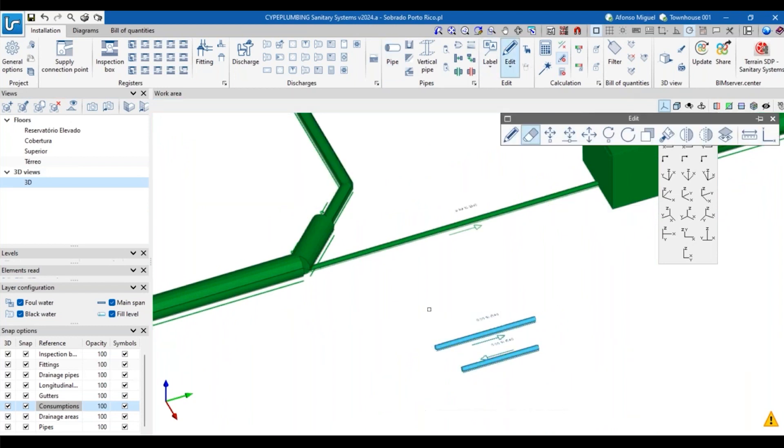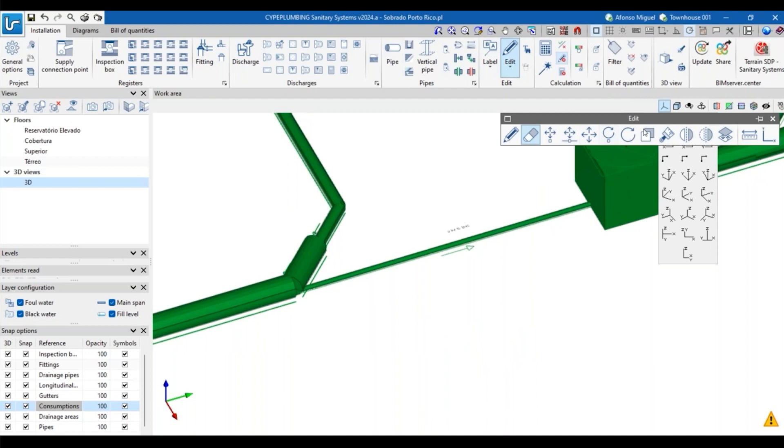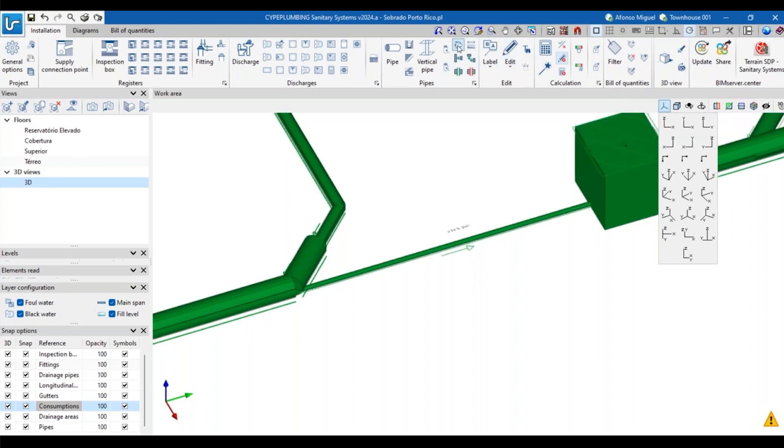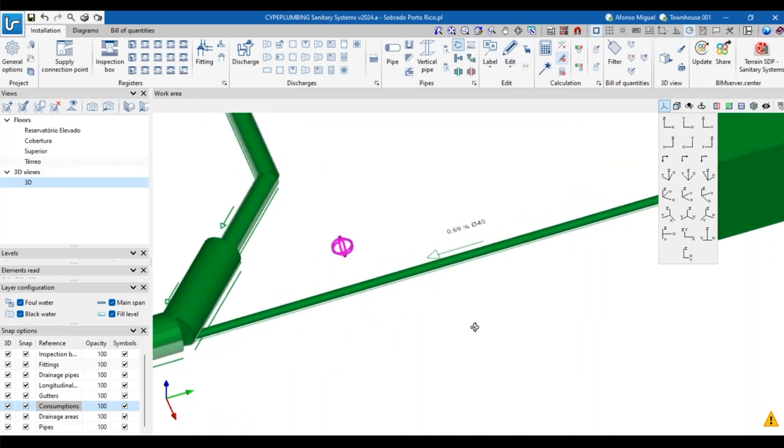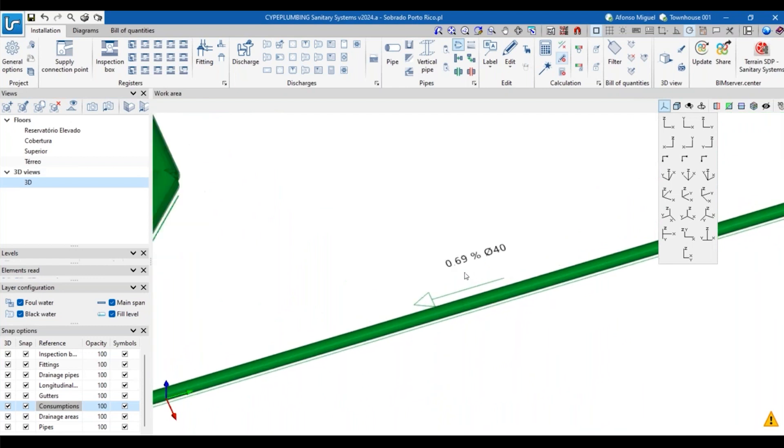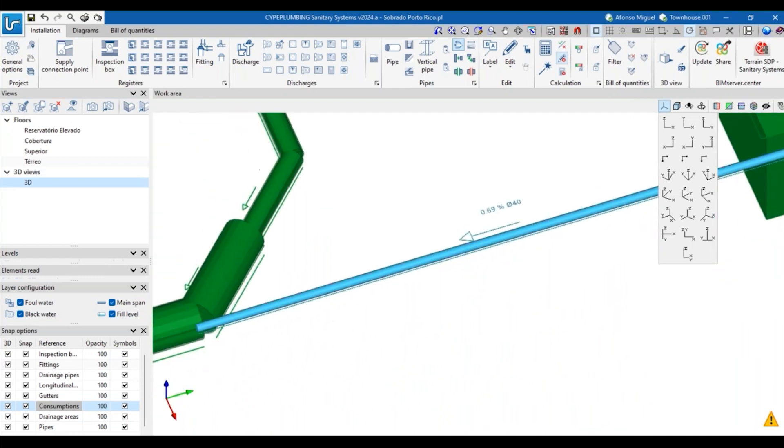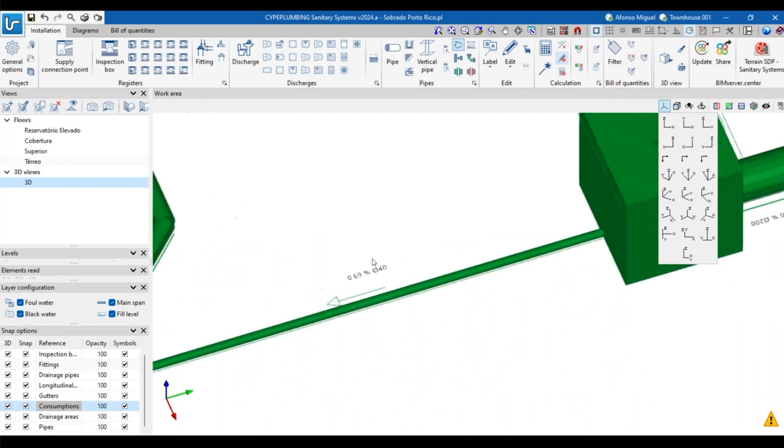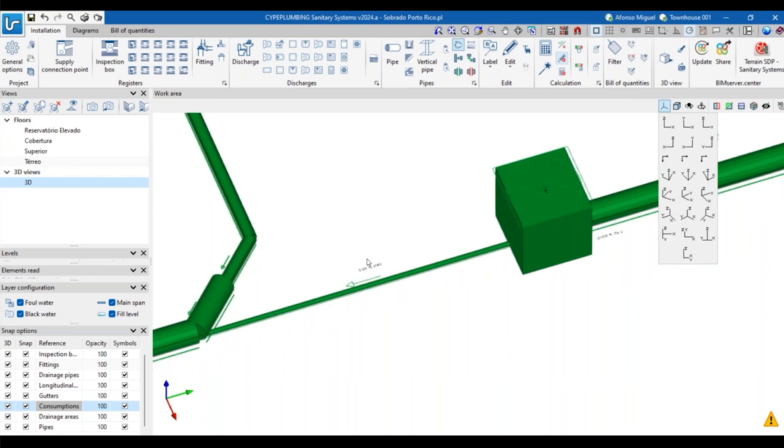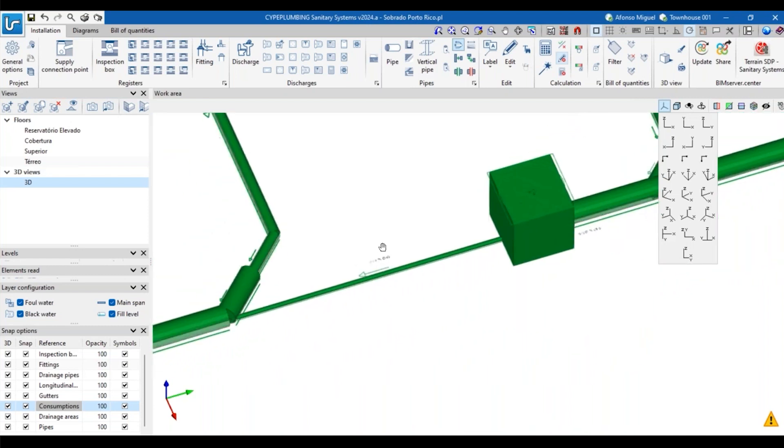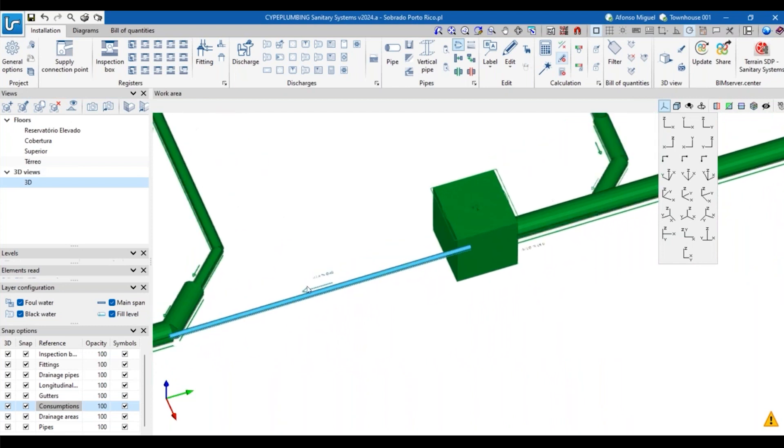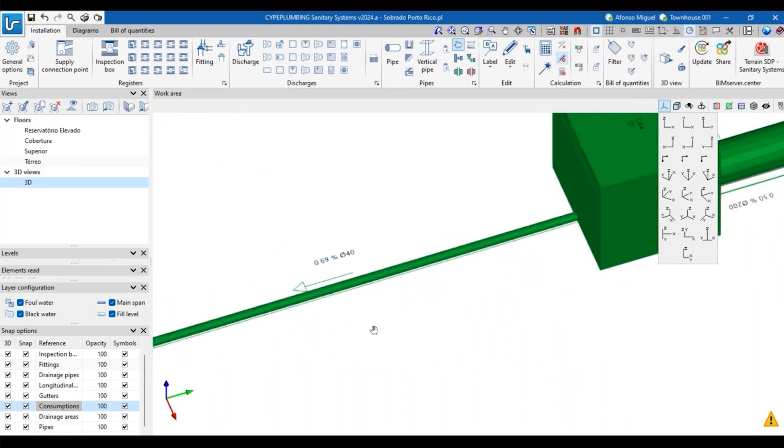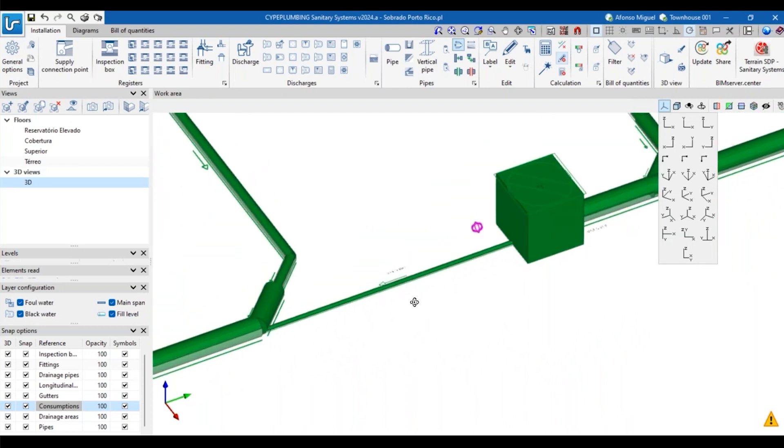Let me delete this part, but I have here one option that can be used - this one - to change the flow direction. So I can click here and it's going to be changed very easily. We can also see that when I connected this pipe that was here to that box, we can see now the slope: 0.69 percent. So the software will represent this information to us, which is very useful.